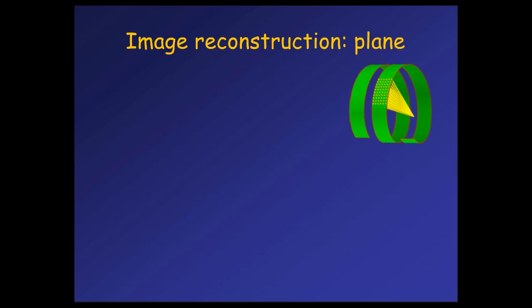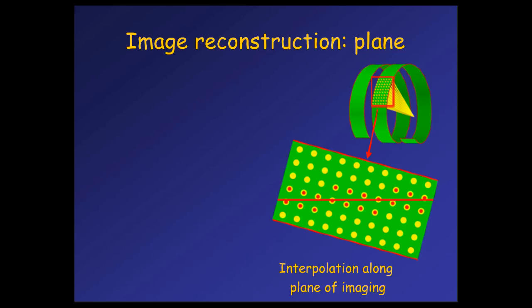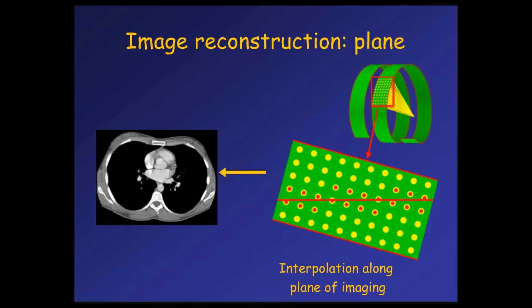You have this helical data set. What do you do with that? You have to reconstruct images. You can reconstruct images along any plane that you want. The helical data set is used to generate volumetric data. To generate a specific image along a specific plane, you simply do interpolation of the data from the detectors that were along that plane when the patient gets scanned. And so you end up with an image.